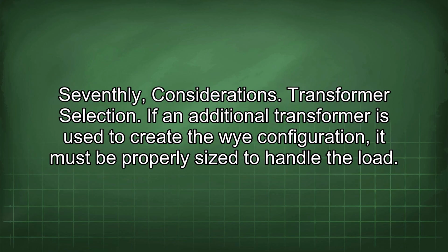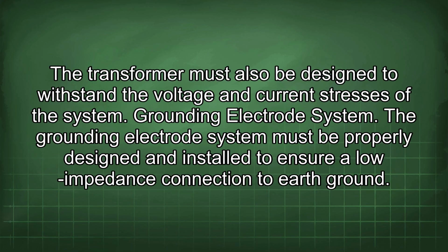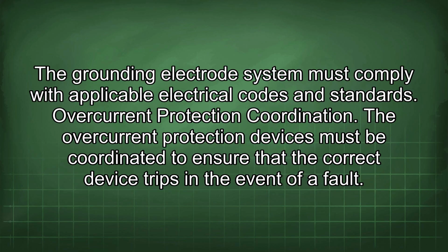Seventhly, considerations. Transformer selection. If an additional transformer is used to create the Y configuration, it must be properly sized to handle the load. The transformer must also be designed to withstand the voltage and current stresses of the system. Grounding electrode system. The grounding electrode system must be properly designed and installed to ensure a low impedance connection to earth ground. The grounding electrode system must comply with applicable electrical codes and standards.